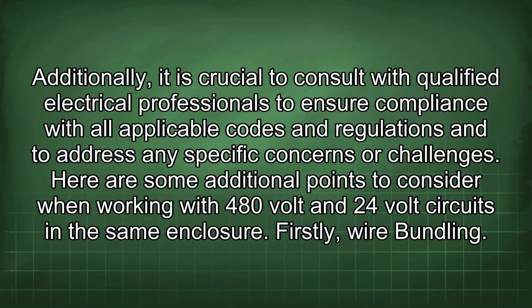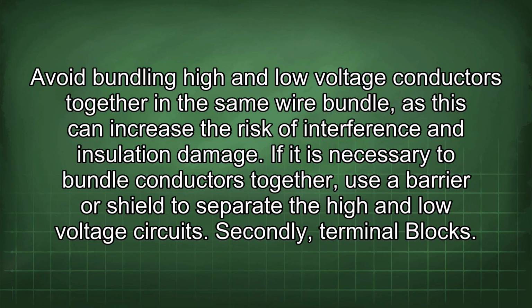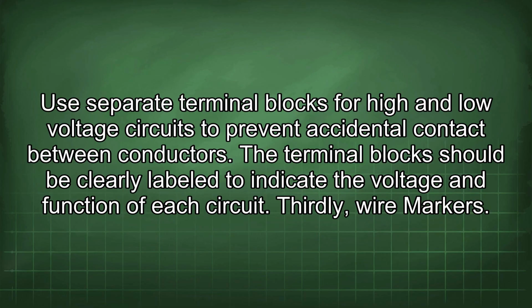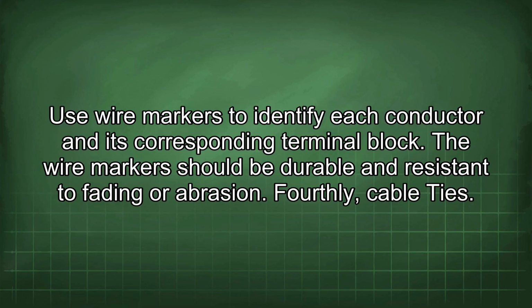Firstly, wire bundling. Avoid bundling high and low voltage conductors together in the same wire bundle, as this can increase the risk of interference and insulation damage. If it is necessary to bundle conductors together, use a barrier or shield to separate the high and low voltage circuits. Secondly, terminal blocks. Use separate terminal blocks for high and low voltage circuits to prevent accidental contact between conductors. The terminal blocks should be clearly labeled to indicate the voltage and function of each circuit. Thirdly, wire markers. Use wire markers to identify each conductor and its corresponding terminal block. The wire markers should be durable and resistant to fading or abrasion.